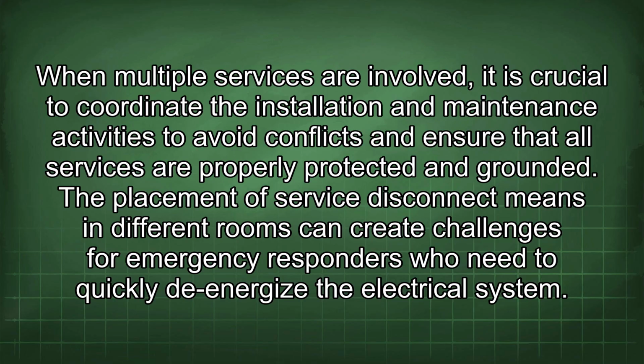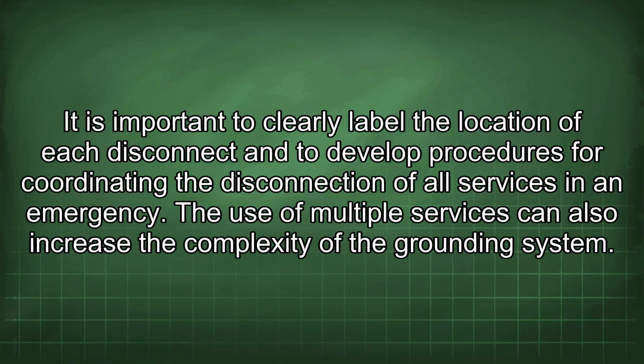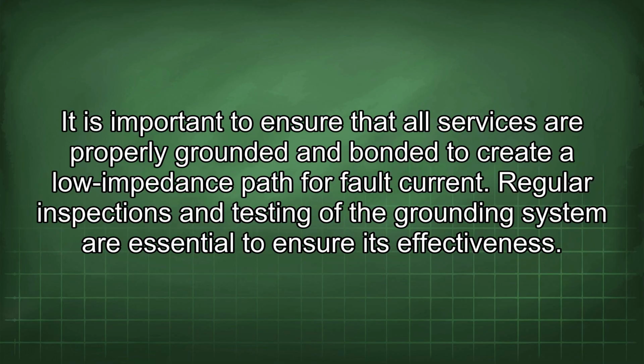The placement of service disconnect means in different rooms can create challenges for emergency responders who need to quickly de-energize the electrical system. It is important to clearly label the location of each disconnect and to develop procedures for coordinating the disconnection of all services in an emergency. The use of multiple services can also increase the complexity of the grounding system. It is important to ensure that all services are properly grounded and bonded to create a low impedance path for fault current. Regular inspections and testing of the grounding system are essential to ensure its effectiveness.